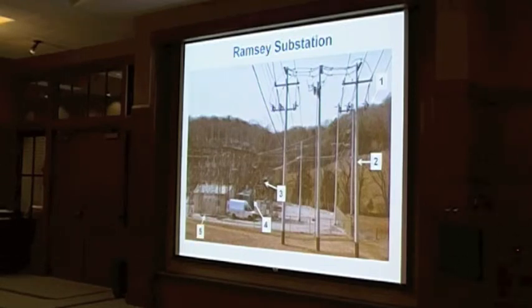Fifth, we upgraded some of the materials inside the control house, which actually runs the substation. We installed brand new relays and new fiber optics, which are a much better communication tool and allowed us to upgrade the inside of that substation.